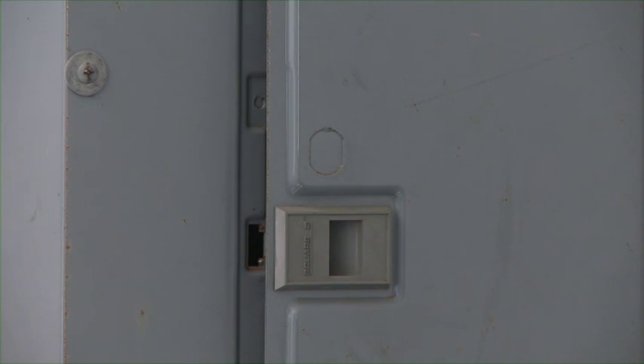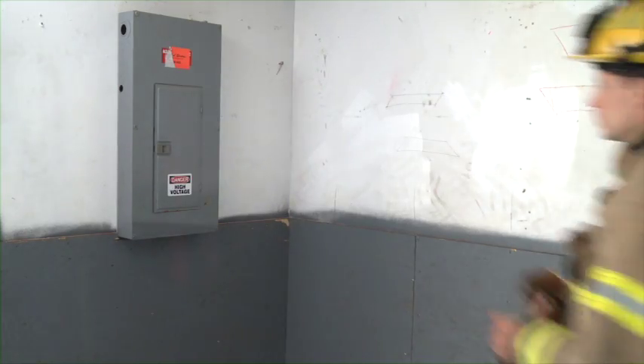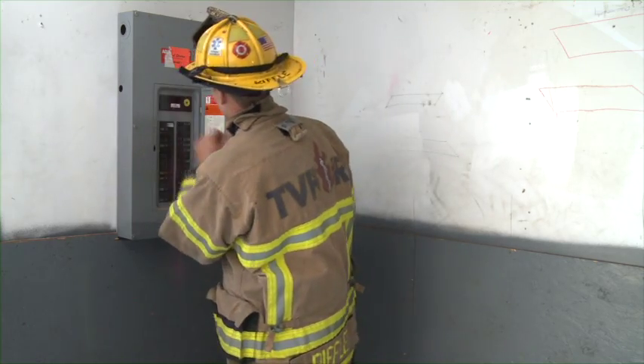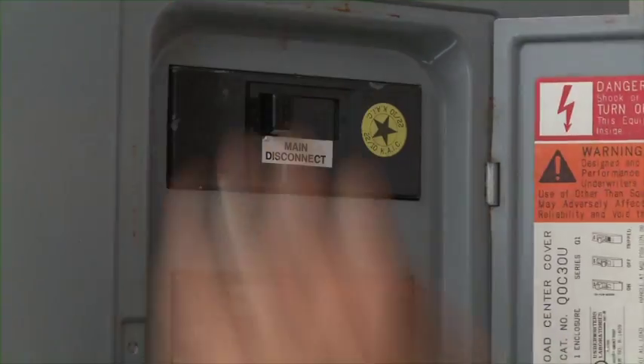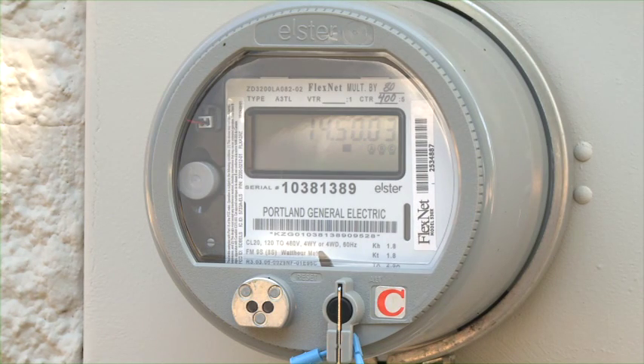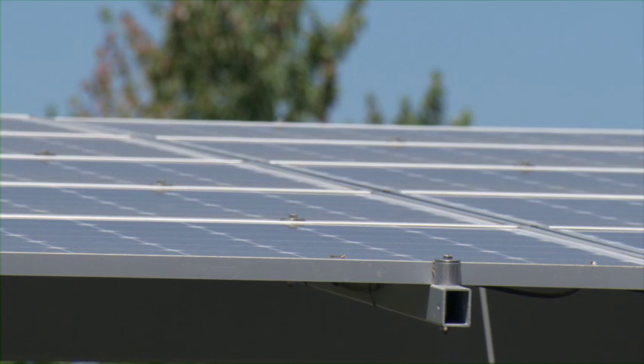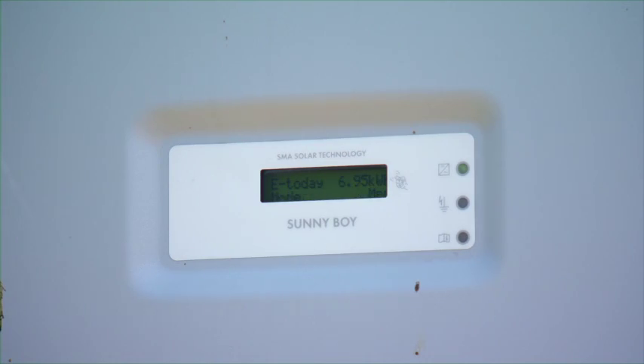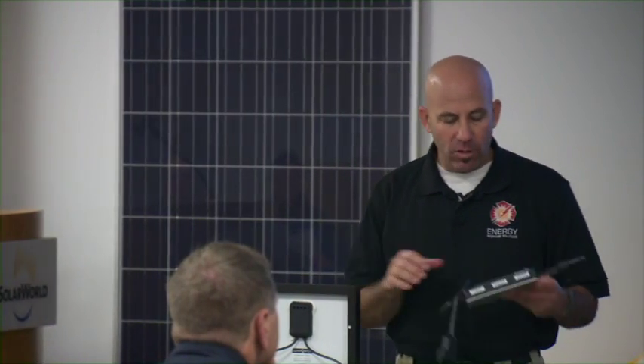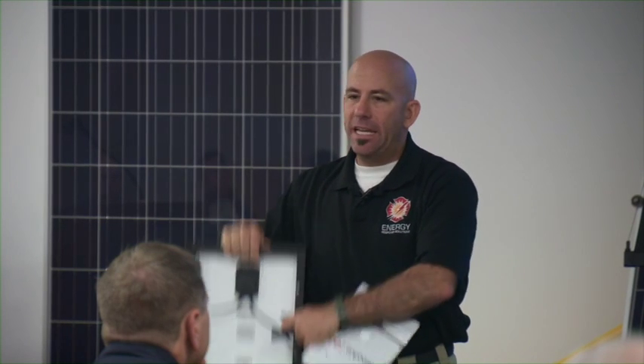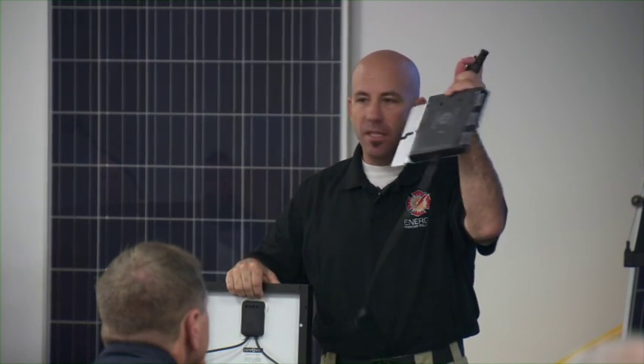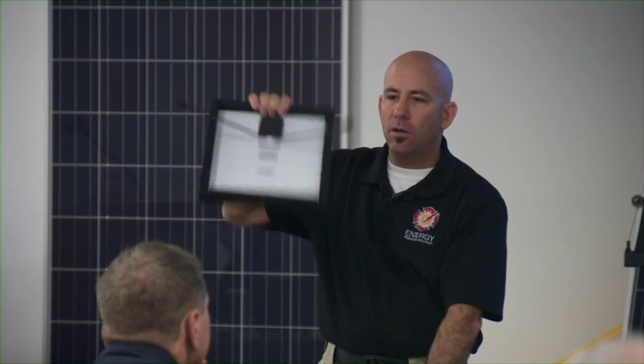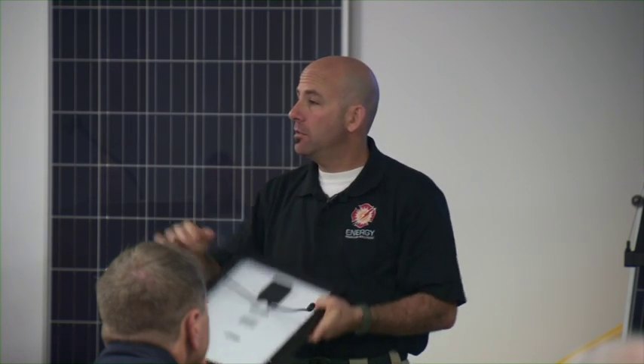You'll want to secure the utilities as best as possible. Shut off the main breaker at the main electrical panel. This will shut off any AC power to inverters, shutting them off and interrupting the power that's entering the building. And remember, the DC power will still be hot from the array down to the inverter if any light is contacting the panels. If you have a microinverter, it's working at the module level. If you turn off the AC power, this thing is off. You only have power from whatever one module is putting out. So if you have 20 modules on a roof, they're all independent.